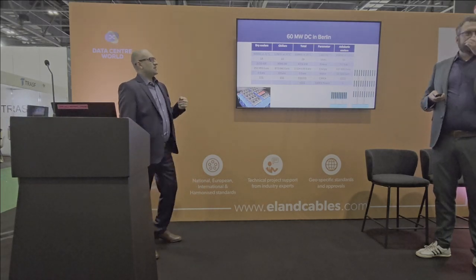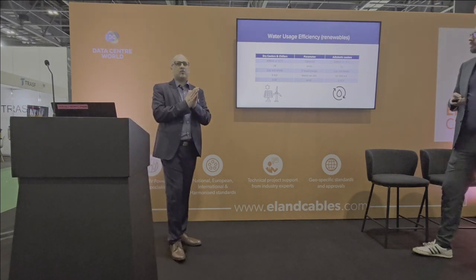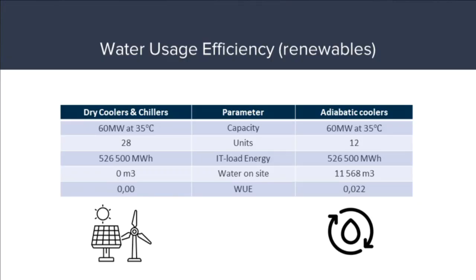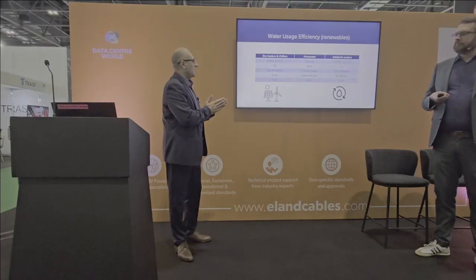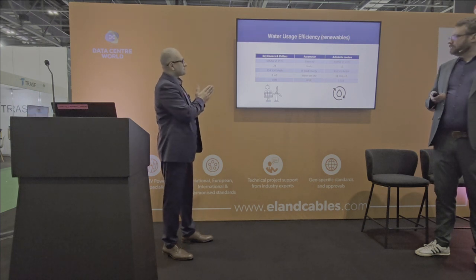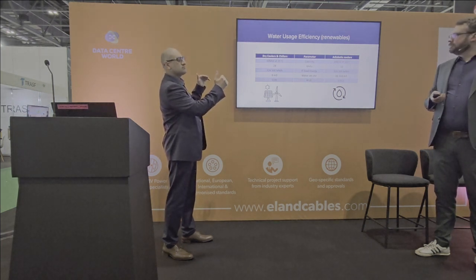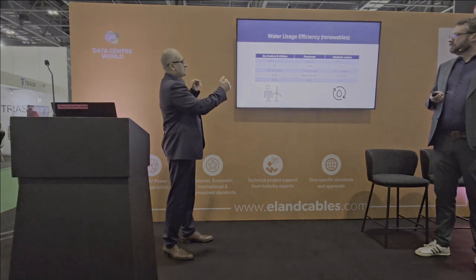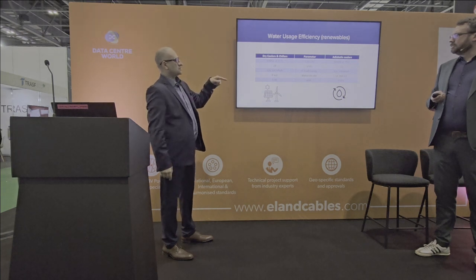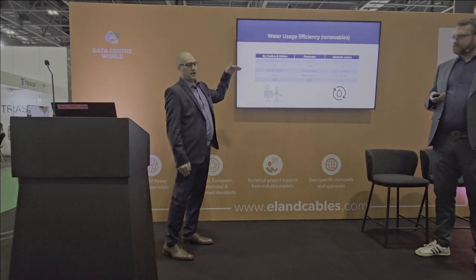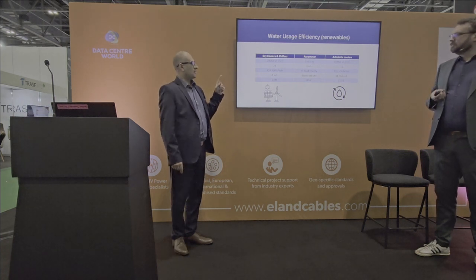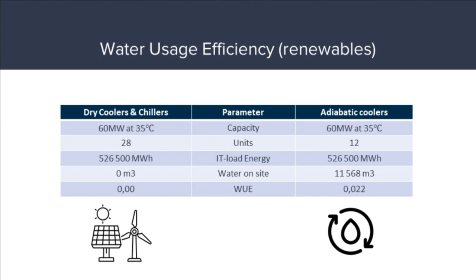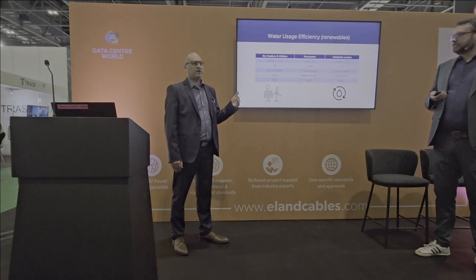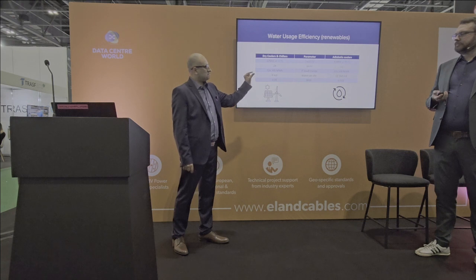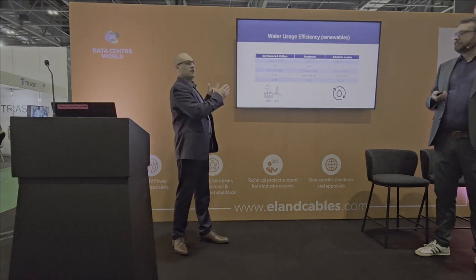And next slide, please. And let's now evaluate what about WUE, what about the impact on the water consumption, environmental impact. So if we take 60 megawatt and have a look at the IT power, IT load during the year, and ratio between water on site in cubic meter divided by the energy IT load which is covered, we will get the factor 0.022. So that proves that our WUE is extremely low. It's not making any harm for the environment, and it's better to use the 11,000 cubic meter of water, but save a lot on energy side.